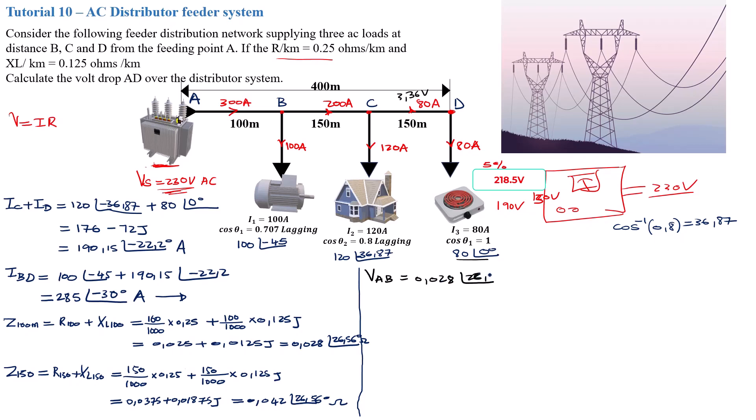V_AB is going to be, where is the impedance? That's a 100 meter section, so it's 0.028 with an angle of 26.56 degrees times our current, 285 with an angle of negative 30 degrees. This gives you a voltage drop of 7.98 with an angle of negative 3.44 degrees volt. So you basically have an approximate voltage drop of 8 volts on this section here.